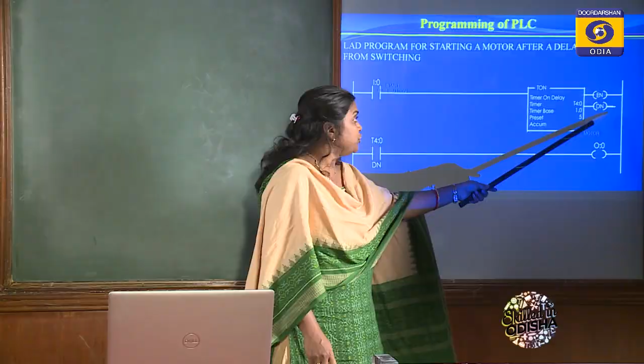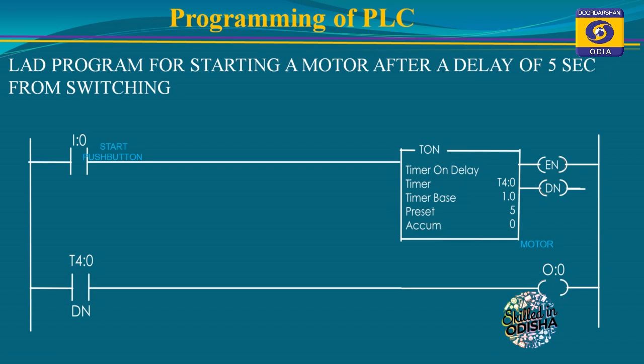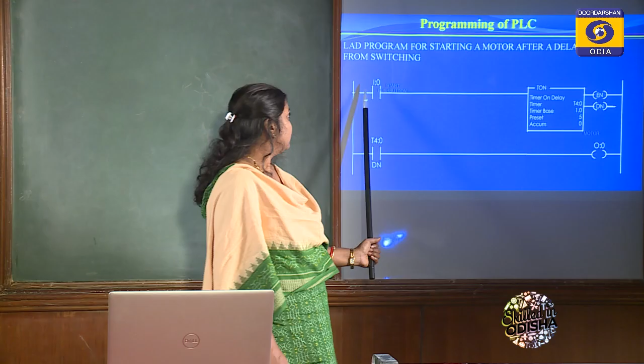Look at this. This is a ladder logic diagram of an output which will operate just after 5 seconds when the switch is on. So a delay of 5 seconds is required, so here we are using a delay timer. On time delay means there is always a requirement that whenever we are switching on the power supply, after some time the device will turn on. Whenever we are turning on the switch of an AC, after some delay it turns on. So that delay will be provided by this timer, the T on delay.